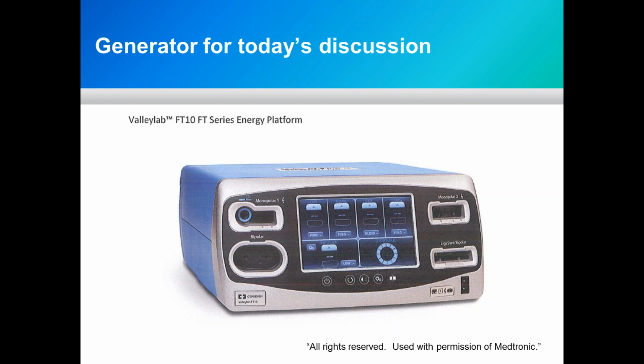The upper left is dedicated to Monopolar 1. The upper right of the screen is dedicated to Monopolar 2. And the Monopolar 2 energy port is where the Valleylab mode is available as well. Bottom left-hand side is the Bipolar output. Bottom right-hand side is the LigaSure output. Another difference here is that the UFP port is integrated into the Monopolar 1 energy output port.